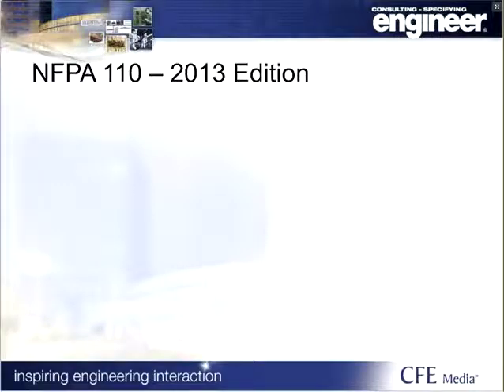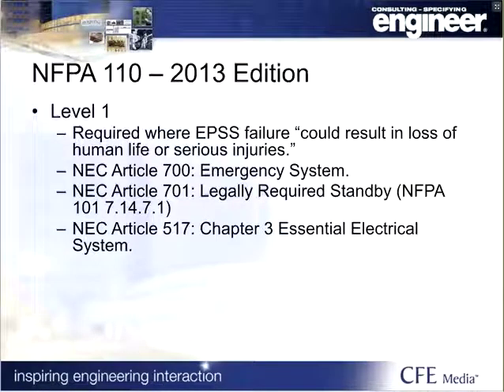Chapter 4.4 in NFPA 110 provides 2 levels for installation, performance, and maintenance of the system. A Level 1 system is required when failure of the EPSS could result in loss of human life or serious injury. Some systems that would fall under this level are NEC 700 emergency systems and NEC Article 517 healthcare essential electrical systems. Some NEC Article 701 systems must comply with Level 1 standards if defined as such. For example, NFPA 101 Section 7.14.7.1 requires Level 1 standby power for elevators addressed by that section.